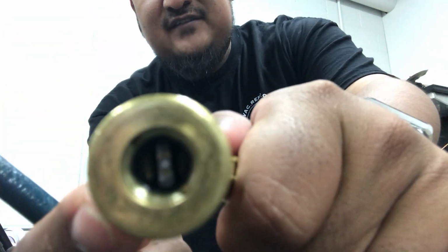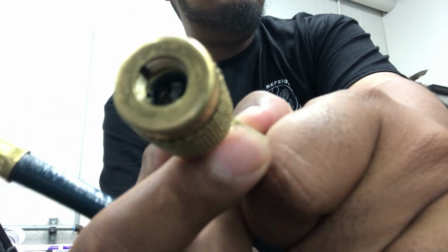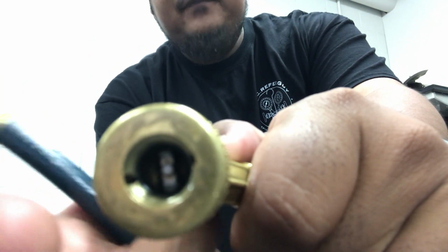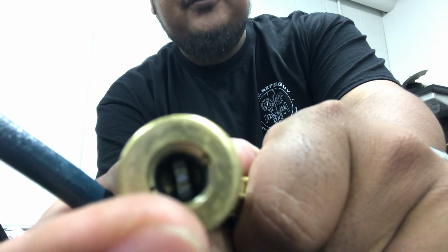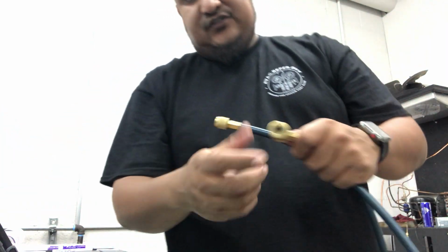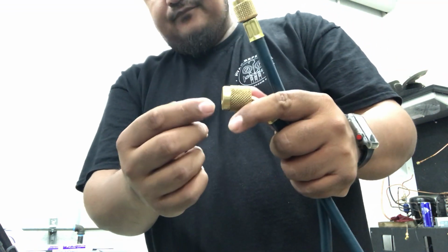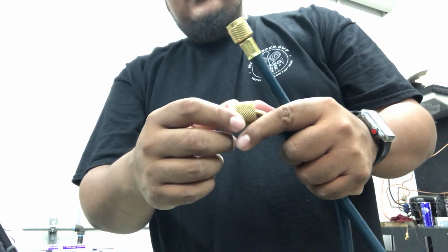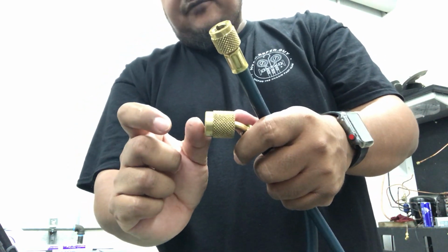So here you can see this is called a low loss fitting, all right? I'll show you the inside here. Can you give me a Schrader? This guy here is what hooks up to your unit. On the inside, it has what's called a depressor, and behind the depressor you have the actual spring. As you hook this guy up into your unit, it will push down on a Schrader core, and you'll see a Schrader core here in a little bit. And then that opens up the refrigerant line for you.